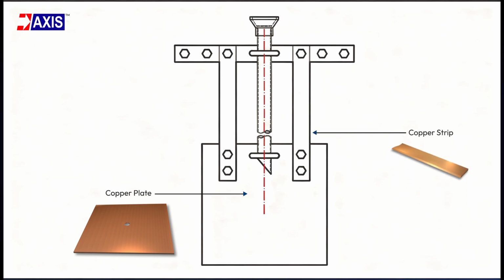Secondly, the copper strip. This strip forms the electrical path between your copper strip terminal and the copper plate buried in the soil. It runs vertically from the plate up to the terminal at the top. When a fault happens, the current travels through the strip before it enters the ground. Its ability to carry fault current depends on its cross-sectional area, and the cross-sectional area is simply the size of the strip when you look at it at its cut face. And you get it by multiplying the width by the thickness. For example, if a strip is 25 mm wide and 3 mm thick, then 25 multiplied by 3 gives you 75 square millimeters. A strip with the highest cross-sectional area can carry more fault current safely.